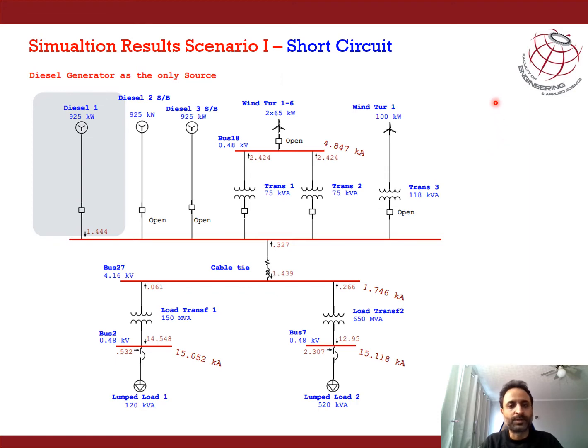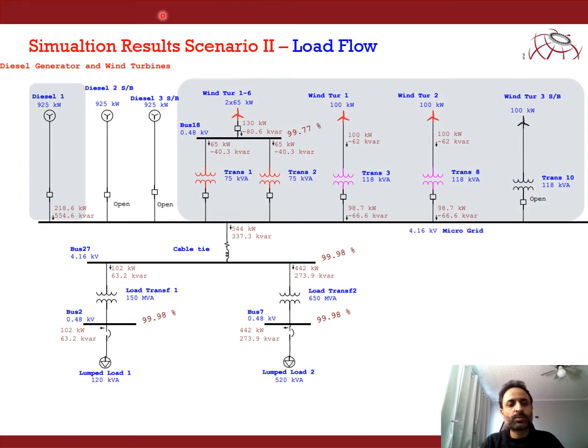The second scenario is with the diesel generator and the wind turbine. So we close the breaker of the diesel generators, and we also close the breakers of the wind turbines. The power flow started from the diesel generators as well as the wind turbines. Now the advantage of having renewable energy here was that the active power generation from the diesel generator has reduced to half. So now we'll consume less fuel, and the emissions from the diesel generator will be less, almost half of what they were when the diesel generator was operating alone.